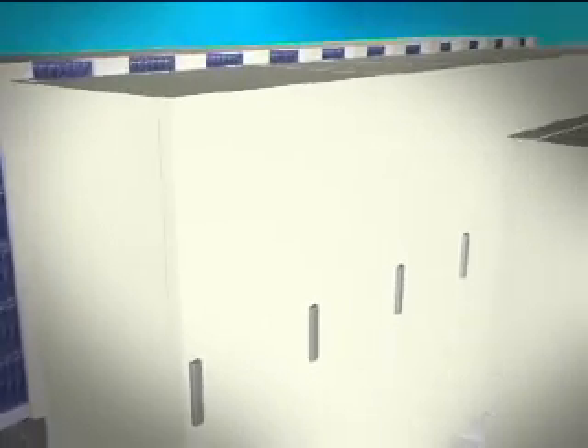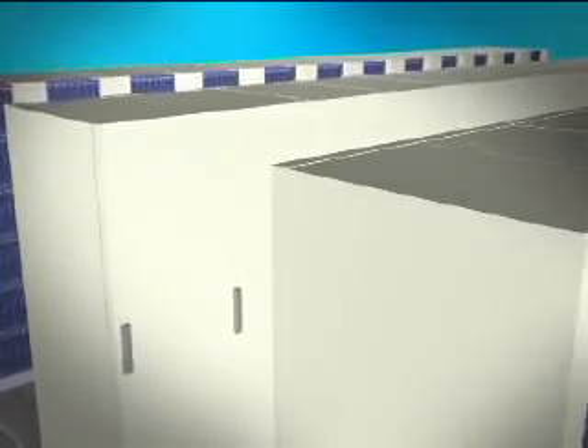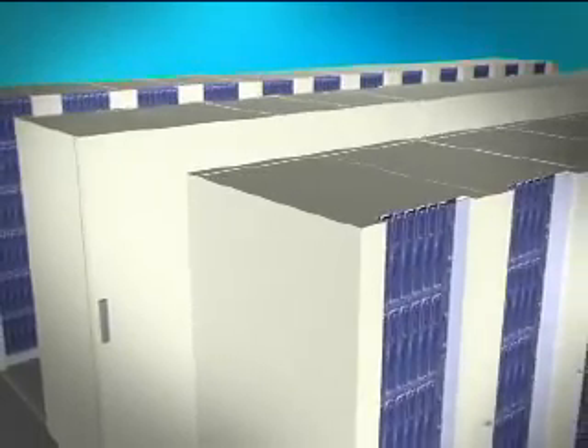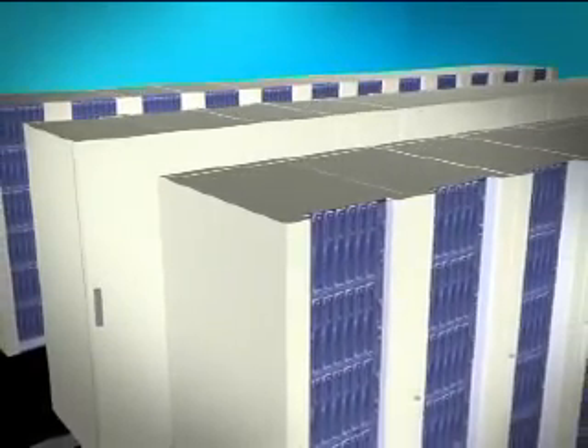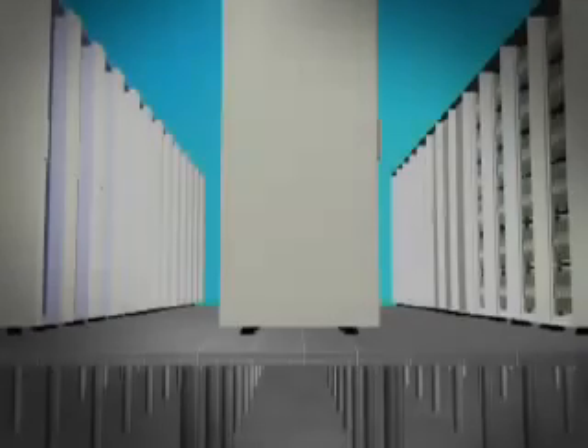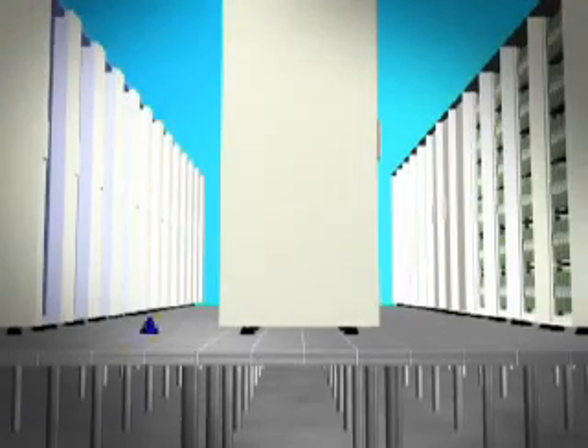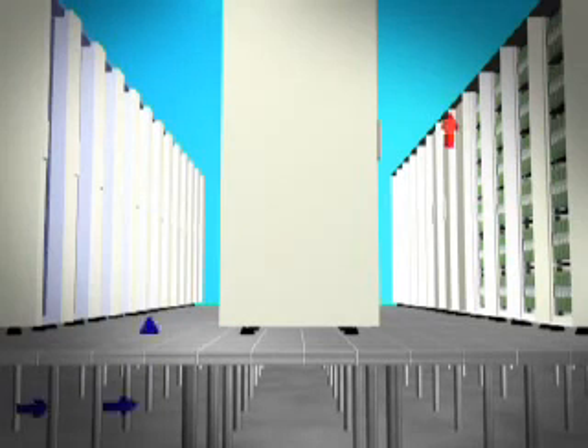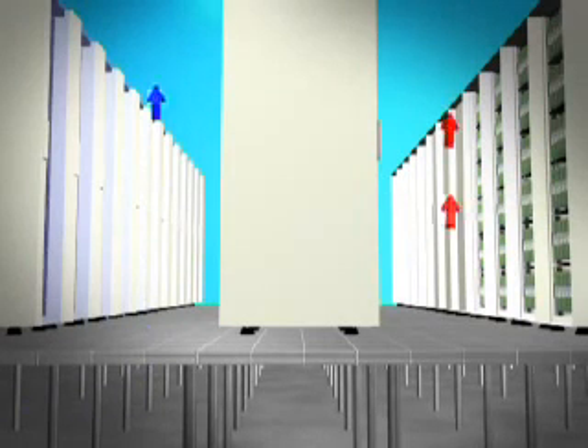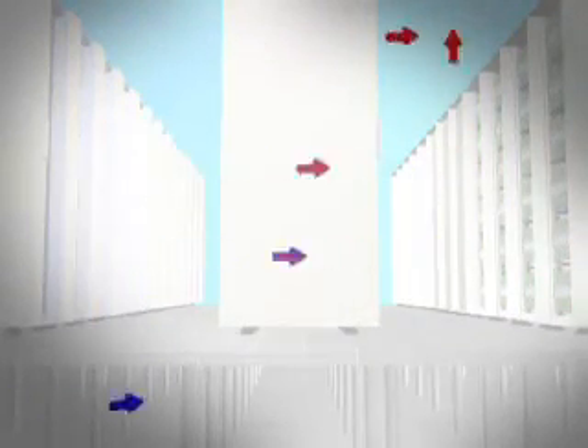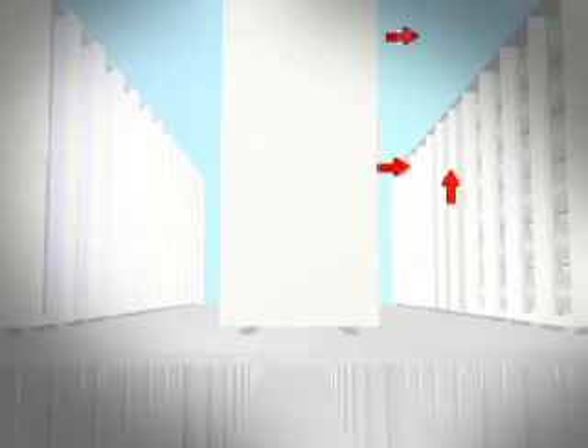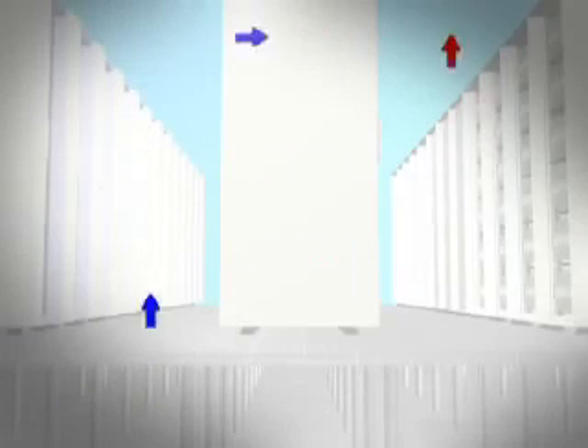Legislation that takes effect by 2008 means that new data center installations will be graded on how environmentally conscious they are. Not only will the IT manager have to focus on speed and power, but he'll be penalized financially for inefficiencies. Traditionally, data centers are cooled using the hot and cold aisle construction. External air conditioning units provide cool air to the front surface of the server. The server then pulls cold air from the cold aisle and exhausts the hot air into the hot aisle. However, hot and cold air can mix, and therefore this method isn't optimally efficient.